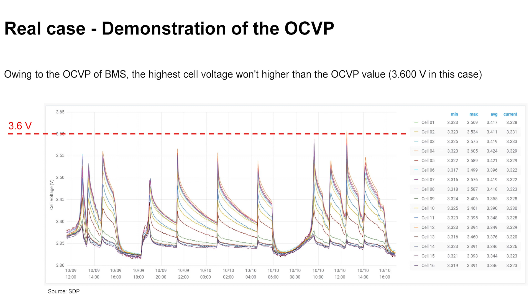The OCVP will continue until the highest cell voltage gradually goes down to the release point of OCVP, 3.400 volt in this case. After the release point of OCVP, the charge relay will turn on and the battery system is ready for charge. If the charger provides current immediately after OCVP release, the cell voltages will rapidly increase to the OCVP value, and then the OCVP starts to function again.